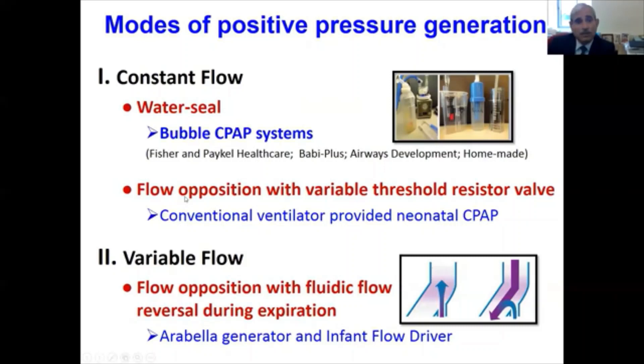Another form of constant flow system is flow opposition with a variable threshold resistor valve. This is what we do with ventilator CPAP. Here the patient's expiratory flow opposes a constant flow from the nasal prongs and generates the CPAP. In contrast, the variable flow system involves flow opposition with fluidic flow reversal during expiration.